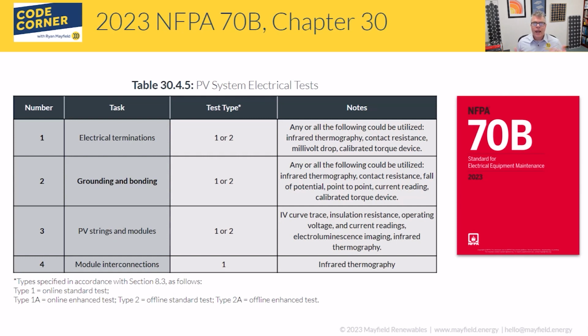And so as you're going out and doing these things, you'll need to follow certain protocols from the manufacturers. 70B is laying out specific timelines on when you would be going out and doing these tests, the intervals between them, and things like that. And so we're going to focus on talking about grounding and bonding, and what some of those tests are. So, the contact resistance, fall of potential, point to point, depends on what the grounding system is that you're testing for. And so we're going to focus in on contact resistance and these earth testers, these digital earth testing tools that you can use.